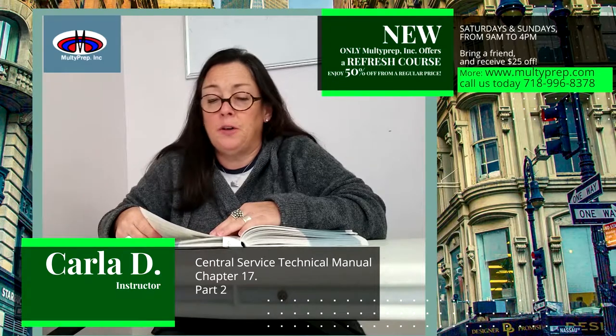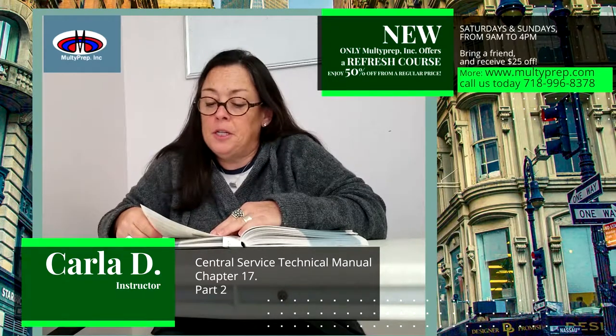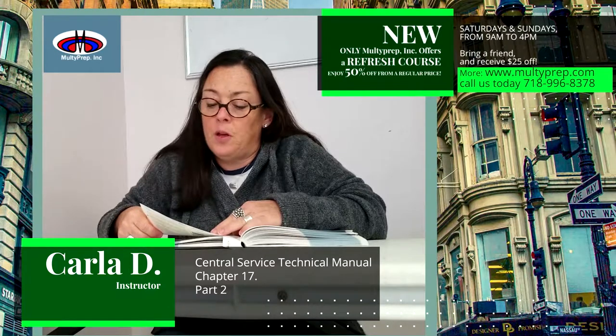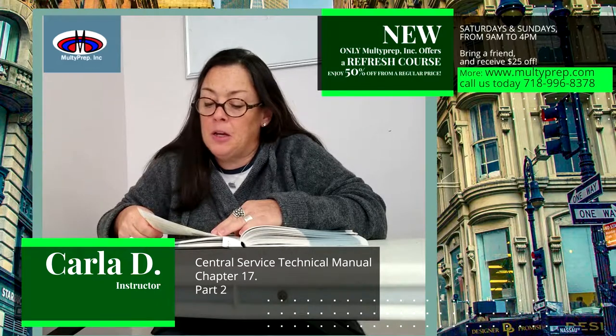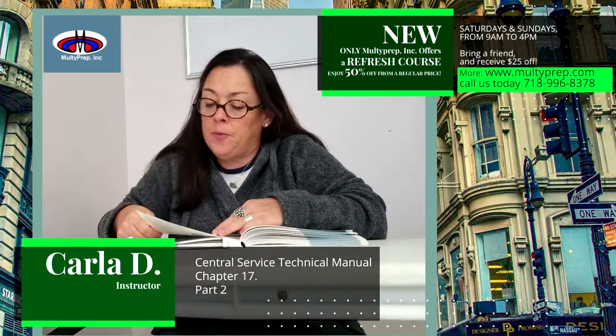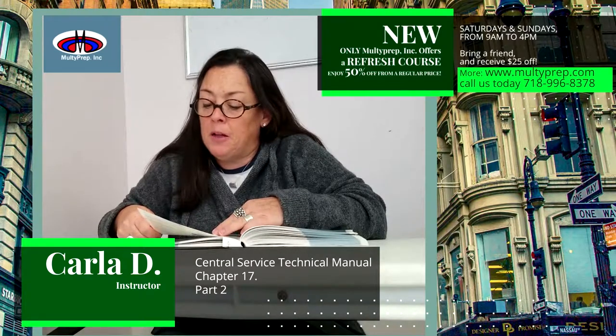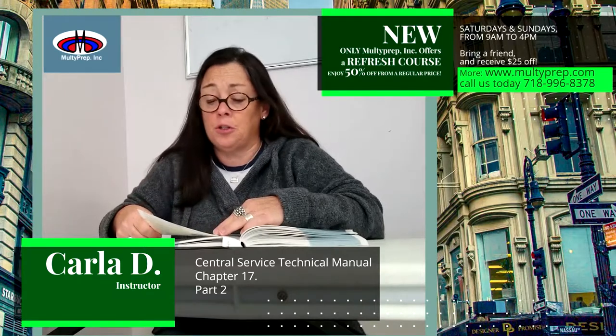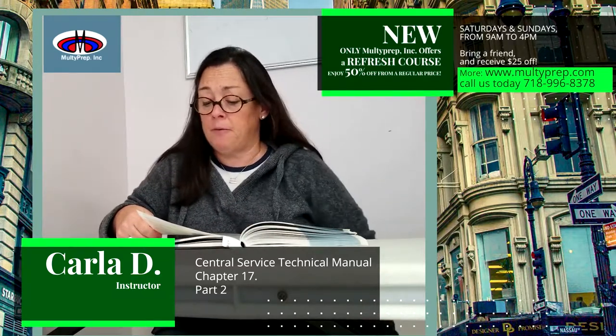Process challenge devices. A PCD is designed to challenge a sterilizer cycle. These packs may be commercially prepared or made at the healthcare facility. PCD packs may contain only a CI, but more frequently they contain a BI and a CI integrator. For those cycles where process challenge devices have been developed, the process challenge device should be used to challenge the sterilization cycle. See 17.10 for an example.